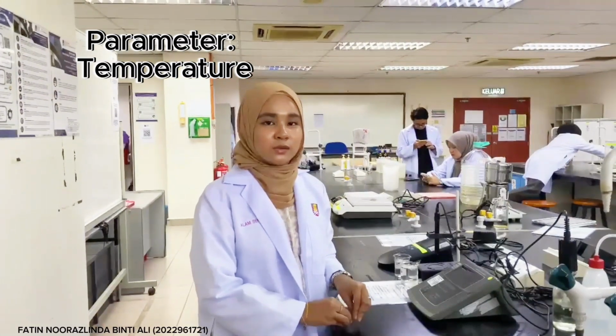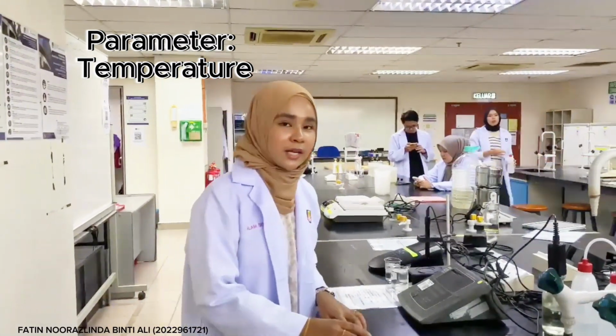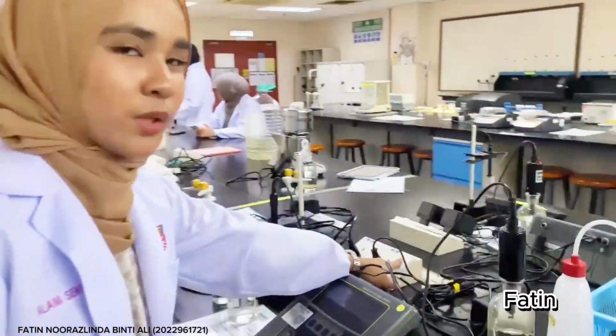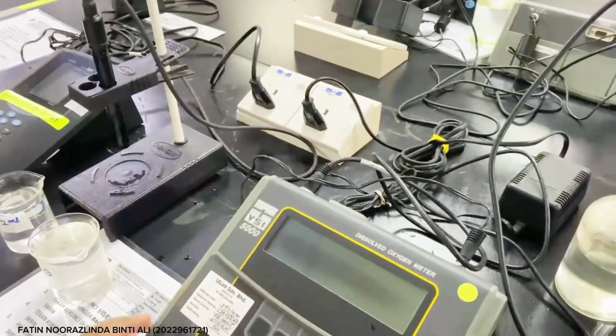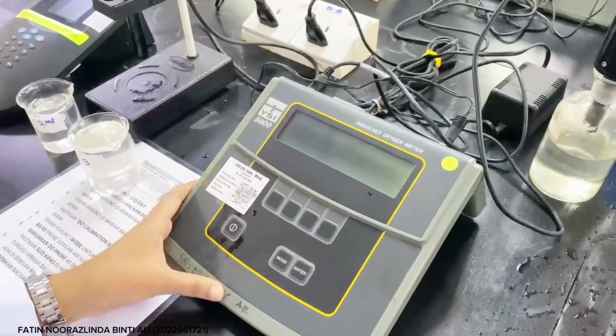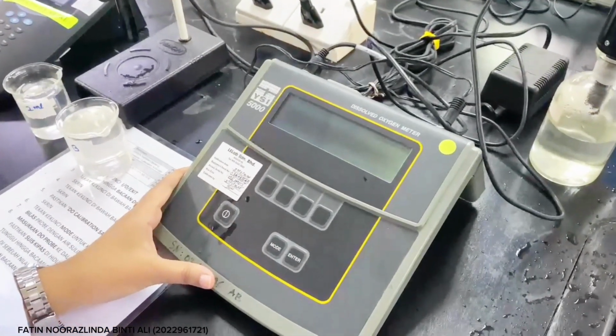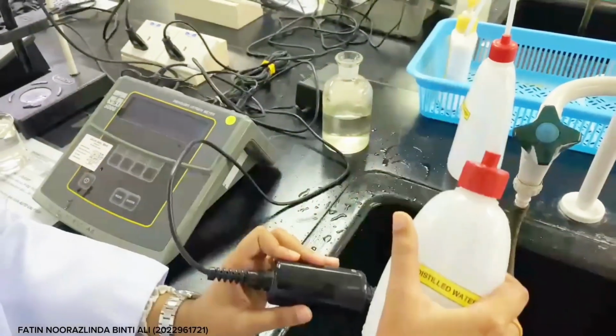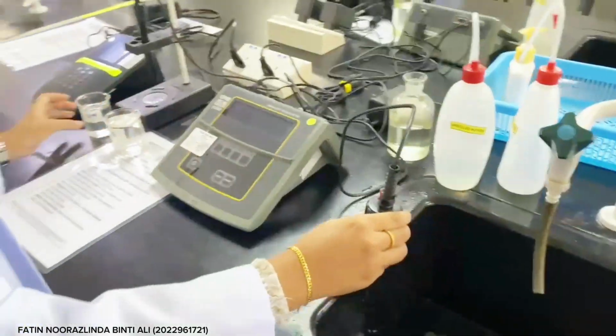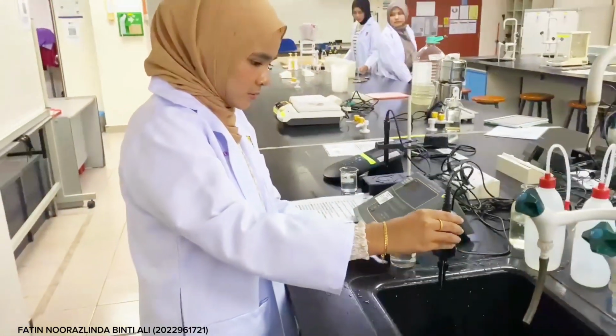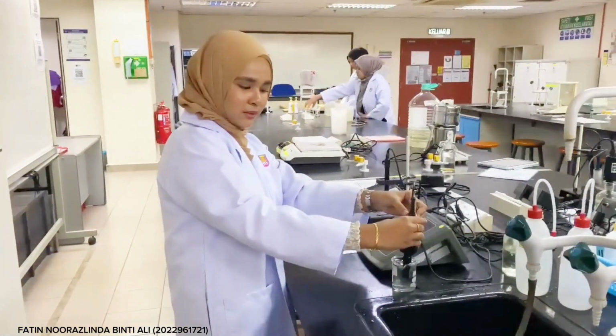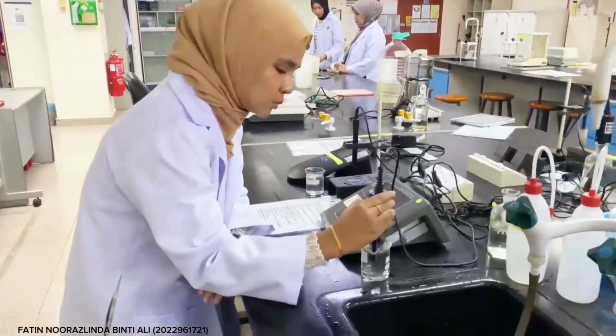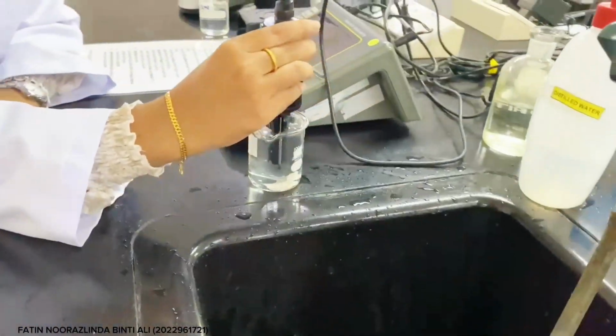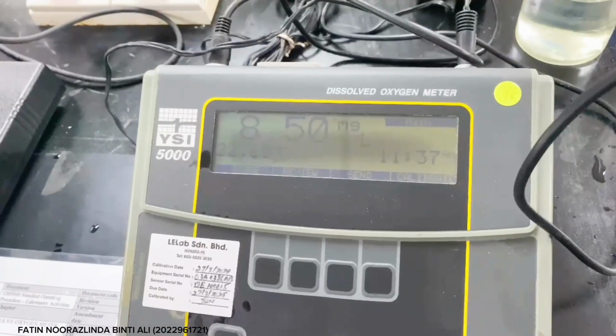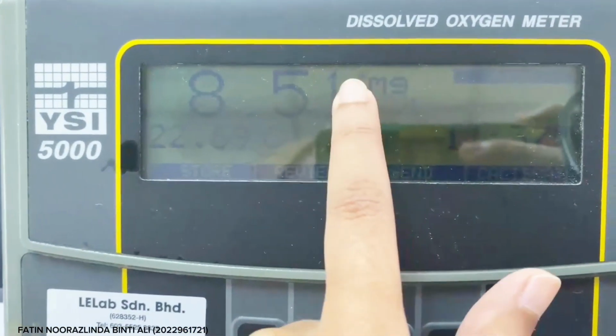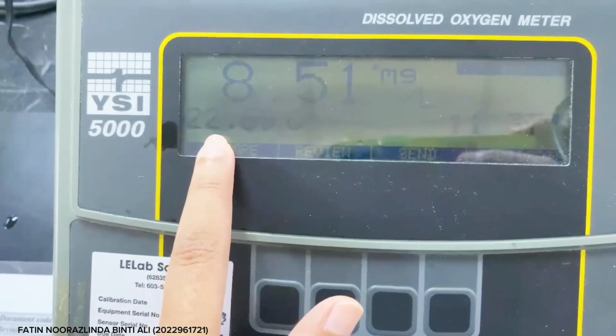For the temperature parameter, we need to use a dissolved oxygen meter to obtain temperature data. First, switch on and plug in the dissolved oxygen meter. Second, press the start button to start the meter. Next, wash the probe using distilled water and insert the probe into the beaker of water sample. Push the red button on the top of the probe to turn the probe on, and the probe will vibrate. Then wait until it beeps and the star symbol appears on the dissolved oxygen meter screen, and the temperature data can be recorded.